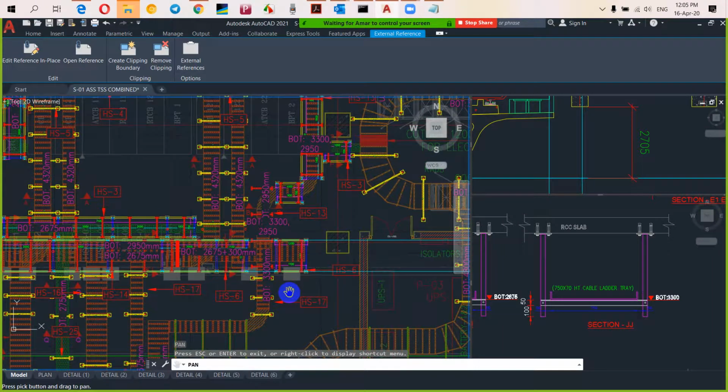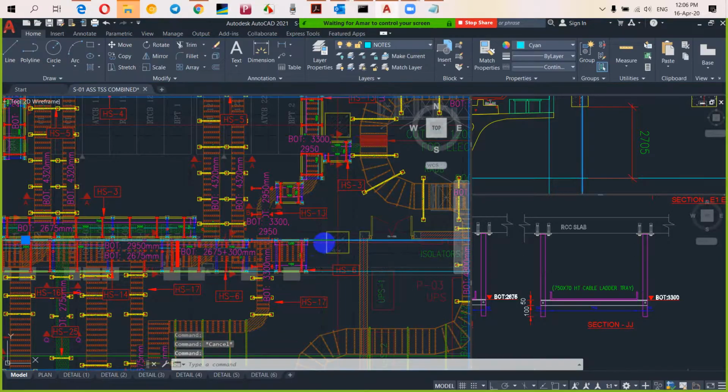So here you see, I'm seeing that your support channels are coming above the panel. Basically the panel height is 3315. If I'm asking 2950, then you have to extend your supports to that level. But my panel height itself is 3315. Then how will you manage here? Because I'm seeing that it is infringing here. Then either I should increase the height of the tray furthermore, or is there any possibility to shift towards here? Because I know that there is no gap. Can you please zoom in yourself and check whether there is any possibility of shifting?